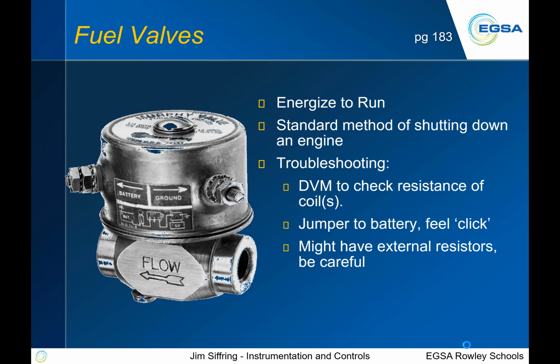Troubleshooting wise, you've got typically a couple of connections. You can check across those pins that you'll see with the nuts on them, to see if there's resistance on those coils. You can jumper to a battery and see if you can feel it click. Just be careful with them though. They might have a current limiting resistor somewhere else, so you might just want to check to see if it clicks, not click and hold.